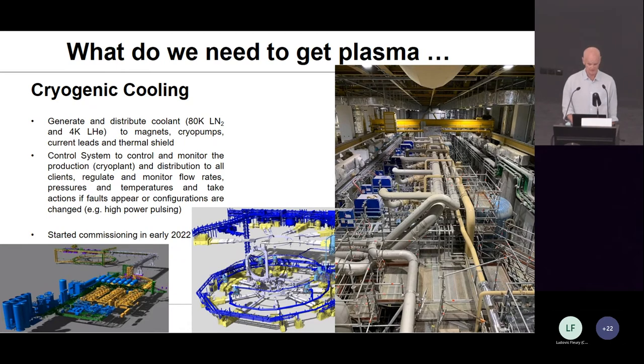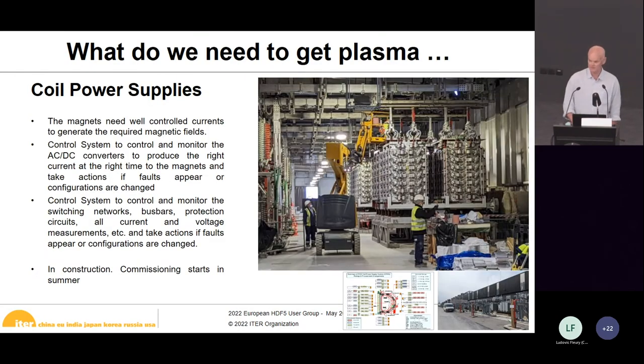We also need cryogenic cooling — the cryo plant produces and distributes nitrogen and liquid helium. The control system has to control and monitor the production, including all pumps, valves, cold boxes, etc., but also distribute it to all clients. Commissioning is ongoing now, and data is being produced. Then we need the coil power supplies to generate currents to the magnets. This is an important system for the control system because it is the main actuator for controlling the plasma. It is currently in construction and commissioning will start next month.